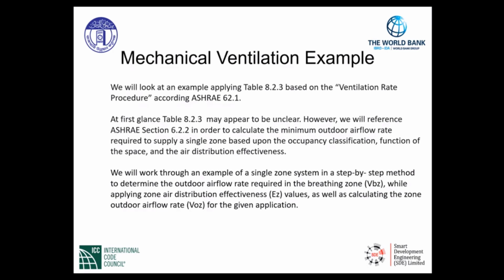Mechanical ventilation example. We will look at an example applying table 8.2.3 based on the ventilation rate procedure according to ASHRAE 62.1. At first glance, table 8.2.3 may appear to be unclear. However, we will reference ASHRAE 62.1, specifically section 6.2.2, in order to calculate the minimum outdoor airflow rate required to supply a single zone based upon the function of occupancy classification and space air distribution effectiveness as well. We'll work through an example of a single zone system in a step-by-step method to determine the outdoor airflow rate required in the breathing zone.